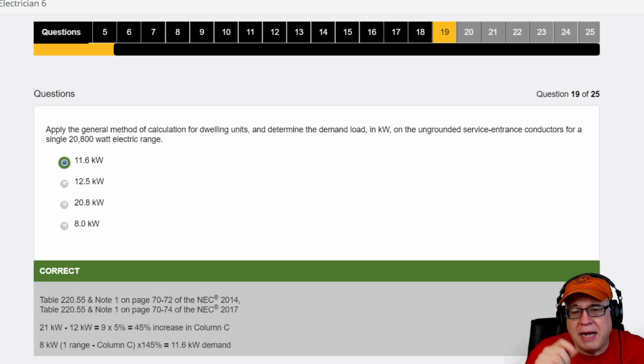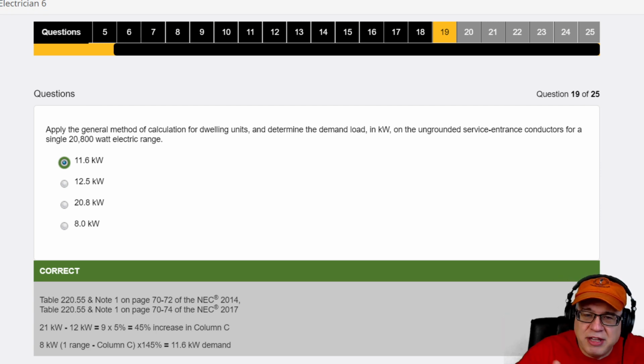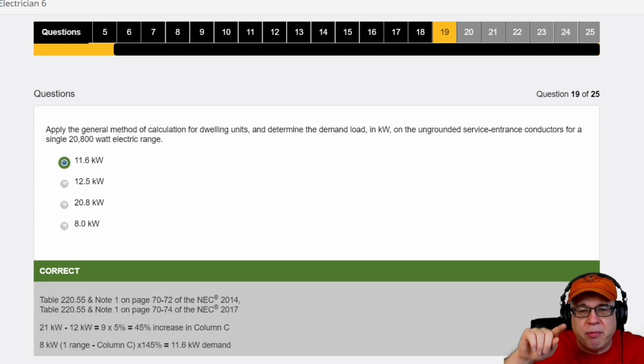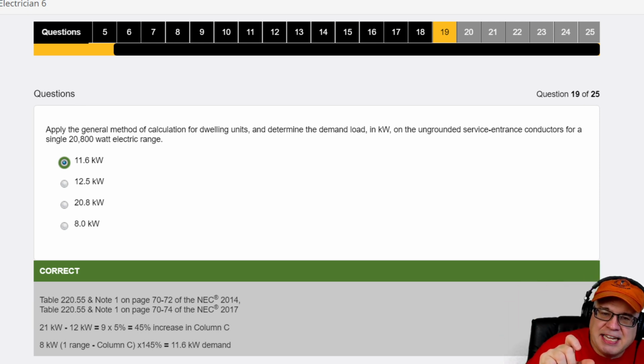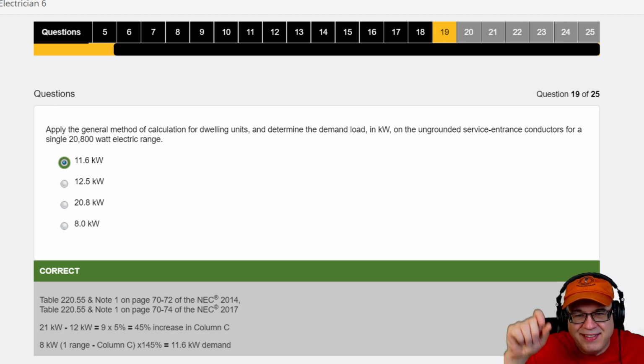And then you just do 21 minus 12, and whatever value you have left, that's your 5 times the 9. 5 times 9 equals 45. Okay, or you could have done the value 8 times 145%. That's a way to do it. Different ways you could have done it. But in this case, you want to remember something. You at least use the 8 kW because that's one range. And then you apply it. You only have to do the 5% as it's over 12, but you're still going to do those 5% for every kW over 12. You're going to apply that to the 8 kW, not to the 12. You with me? That's what gets people.